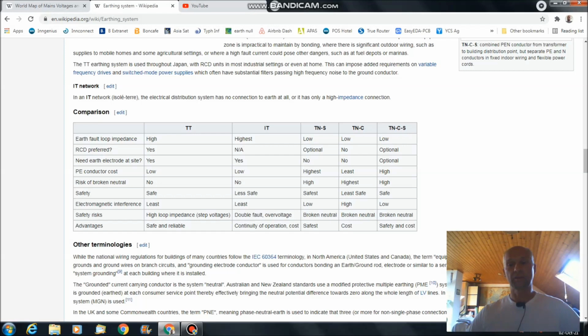But when it comes to using an off-grid inverter, then, as I said before, we are our own utility. So to create a TN system, you have to give this feature to the inverter. The point "need earth electrode at site" refers to a secondary earthing electrode at your property, but you need a primary earthing electrode at your inverter in this case to tap into the earth, so that later on you have a path for fault currents going back to the power source, which is your inverter.